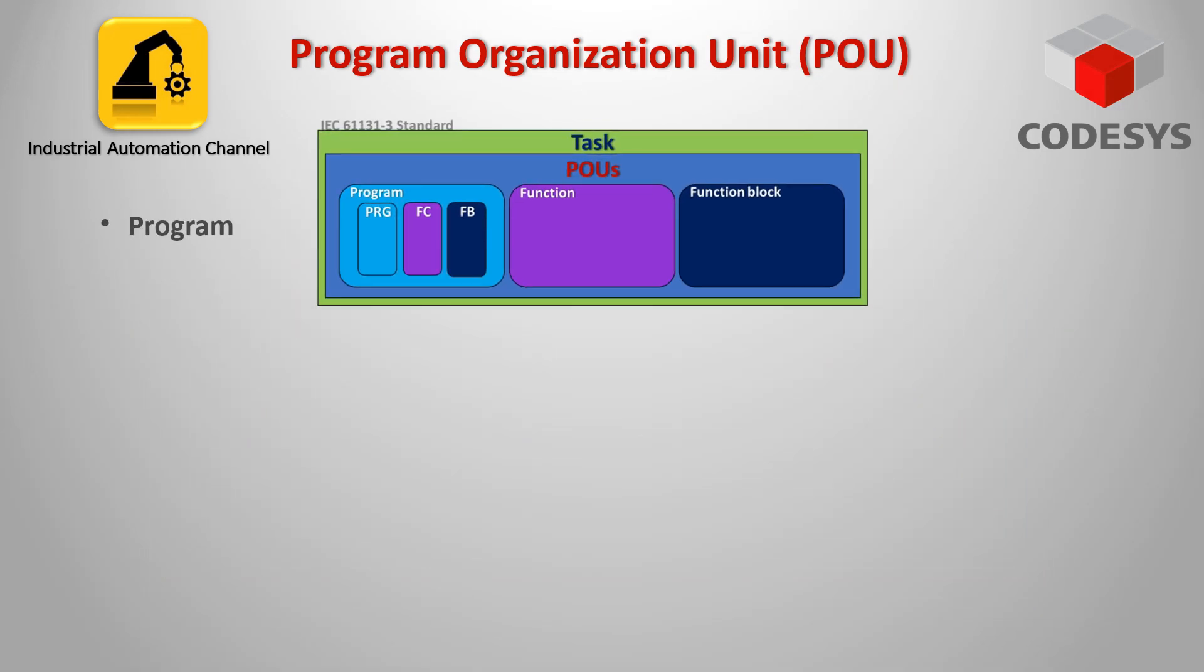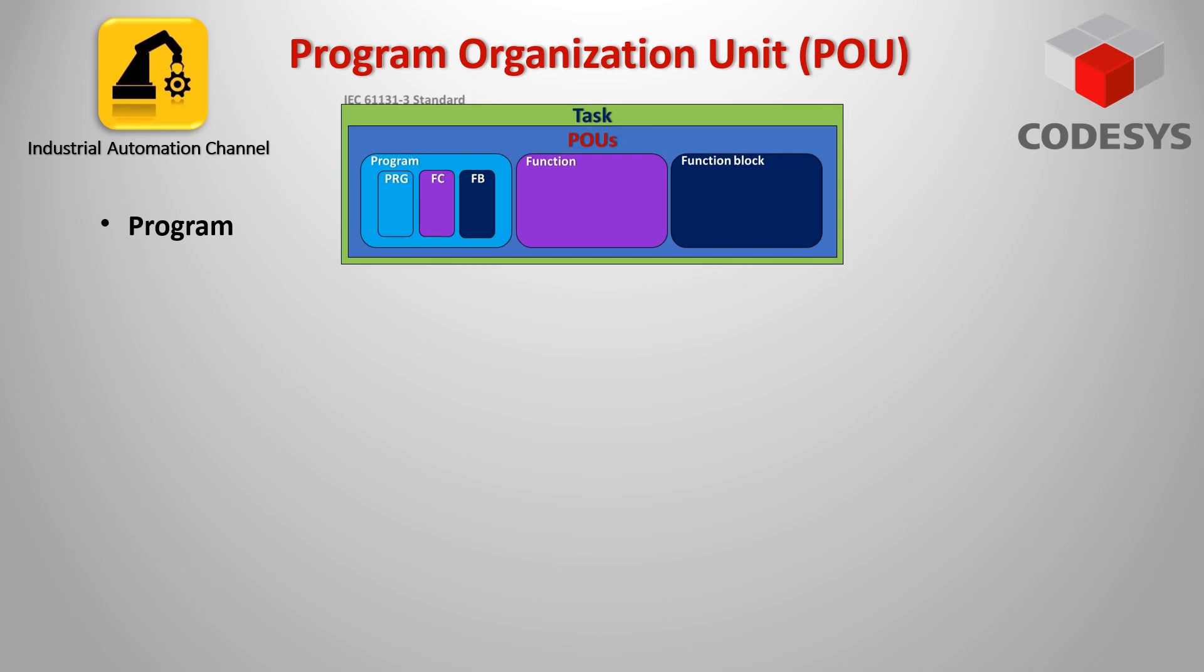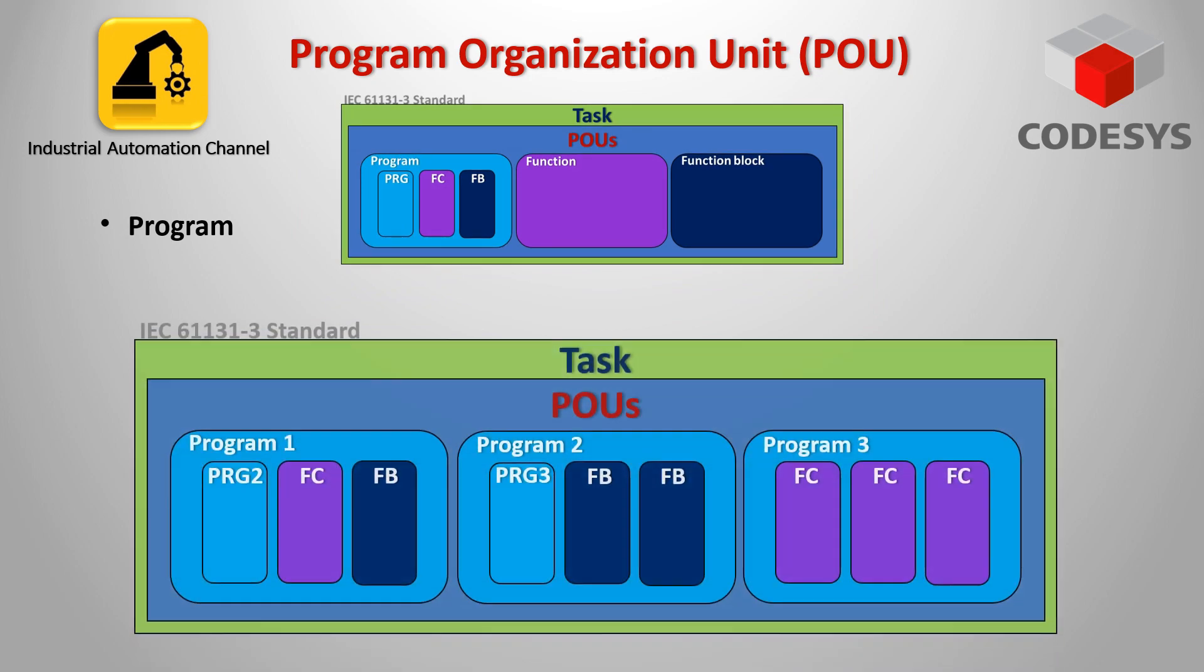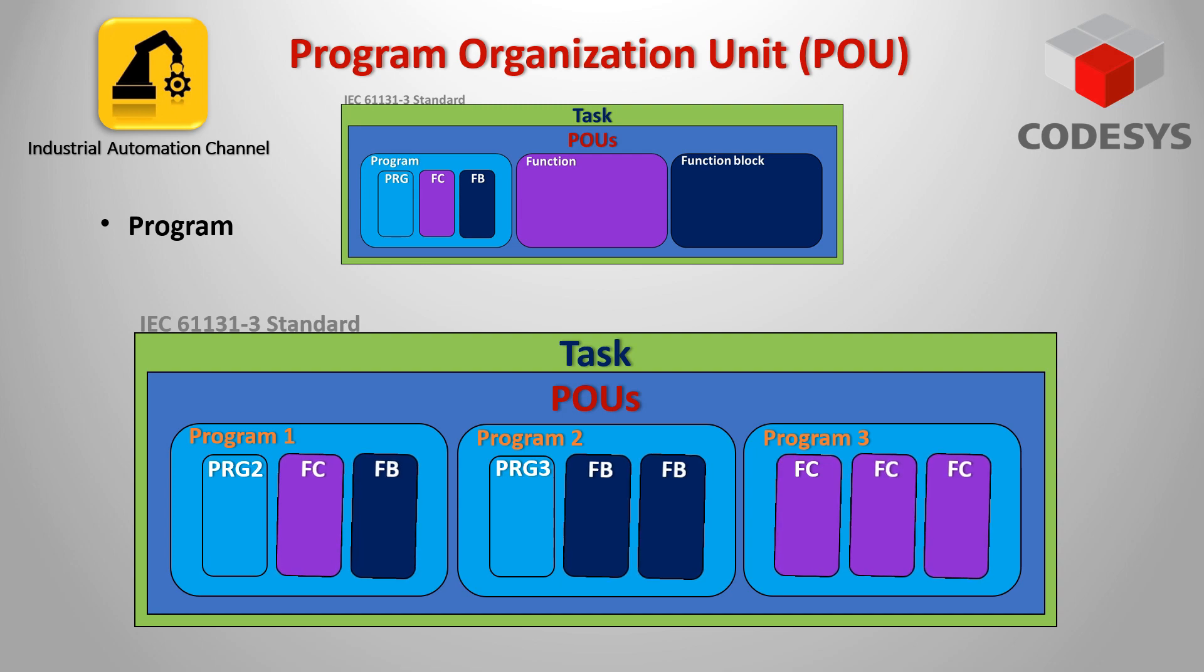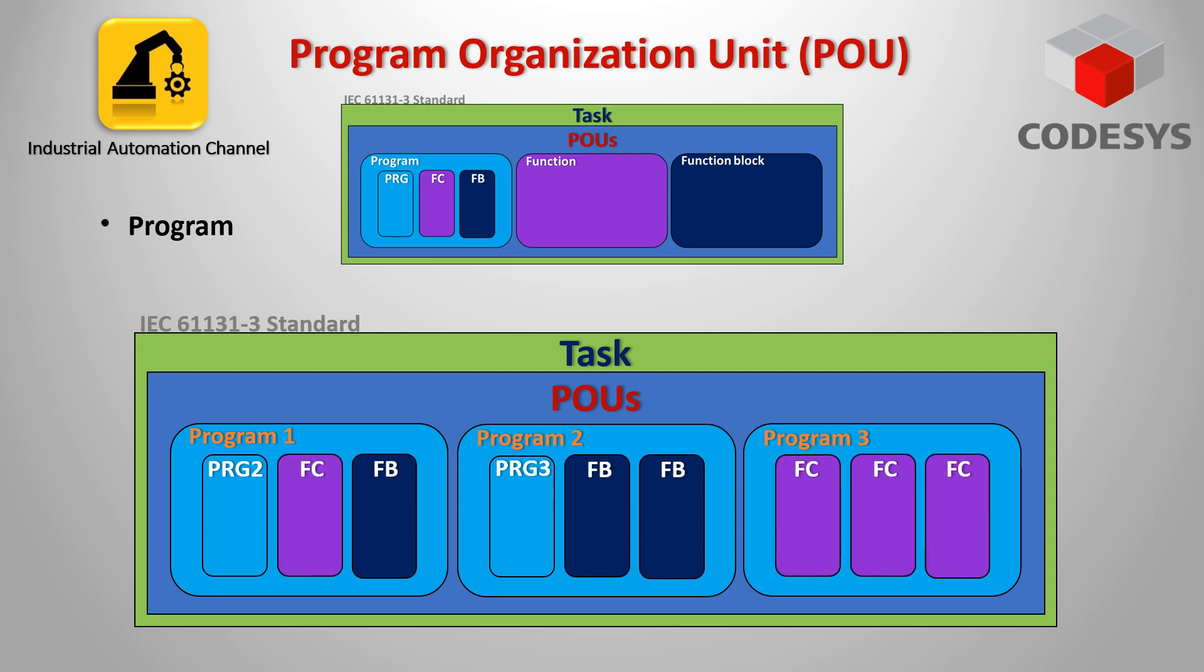The first POU is program. A program is a POU where the application code is written and supplies one or more values during execution. After execution of the program all values are retained until the next execution. Your application can be split up across multiple programs and different function blocks and functions can be called inside the program to avoid having a large and complicated program.